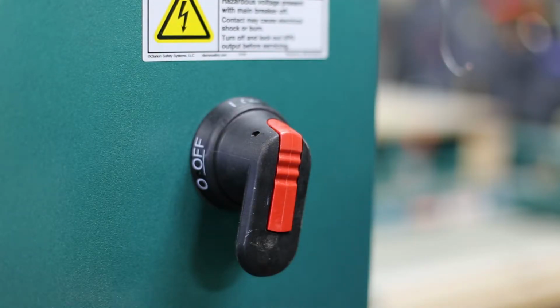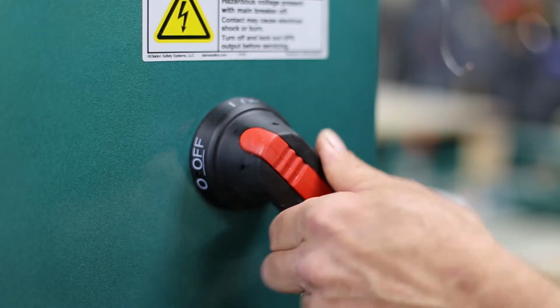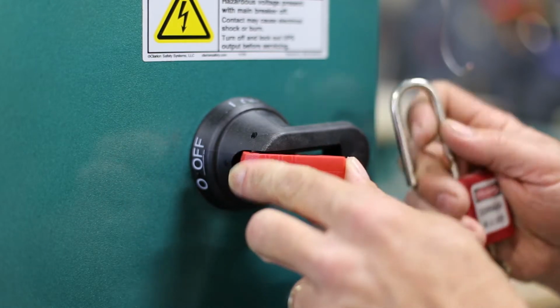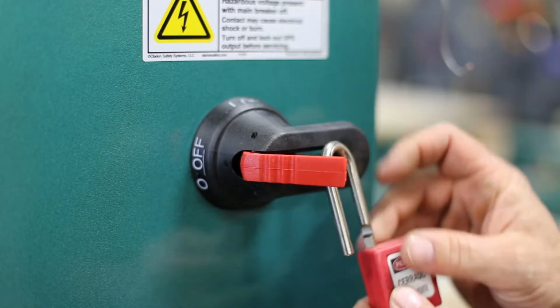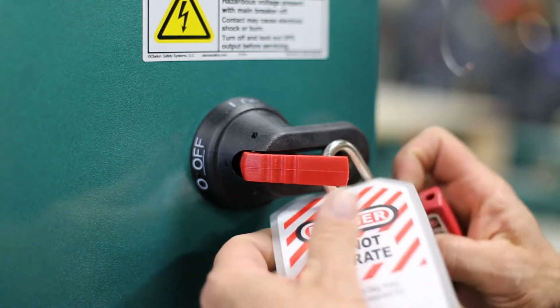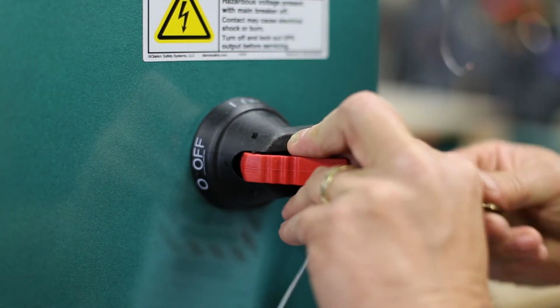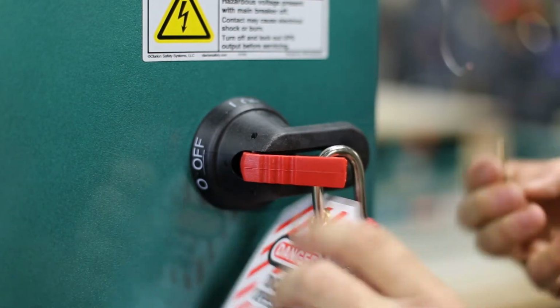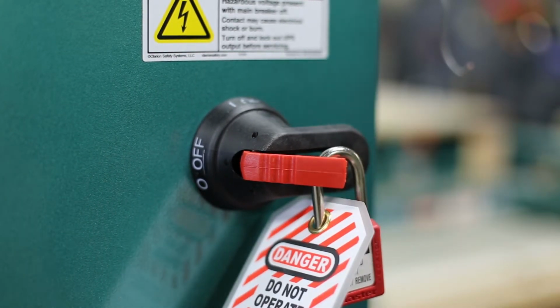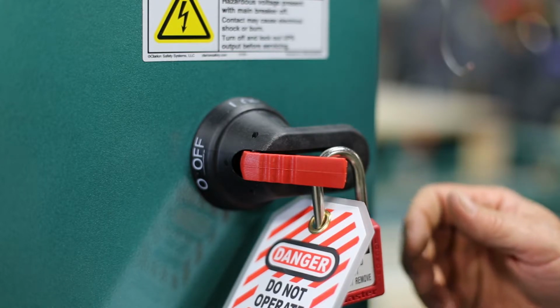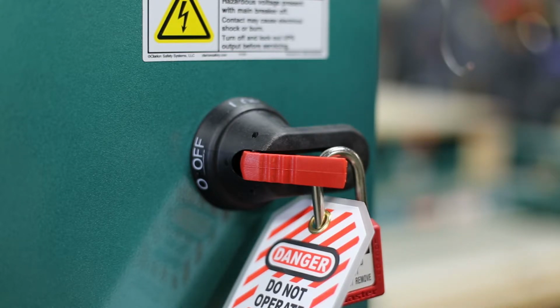Okay, before you start checking your control circuit, you want to lock out, tag out the machine to check ohms on your overloads and your E-stops all the way up to your start circuit. What I advise doing is turning your disconnect to the off position, in this case, opening up this tag out here, put your lock in there, put your tag on it, and then you lock it, turn your key, and pull your key out. Make sure it's locked so now it won't open up. Now the other thing that I'd recommend is if you have power coming in from out on your wall somewhere, go ahead and turn that disconnect off or circuit breaker off and lock out, tag out that one as well.